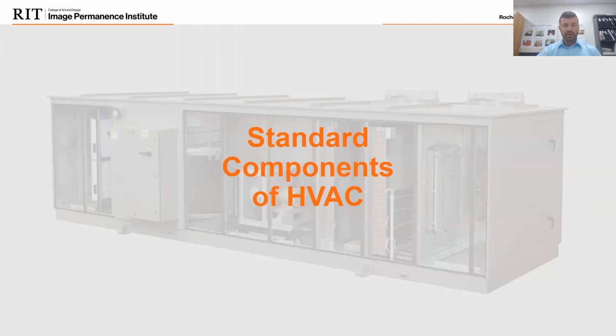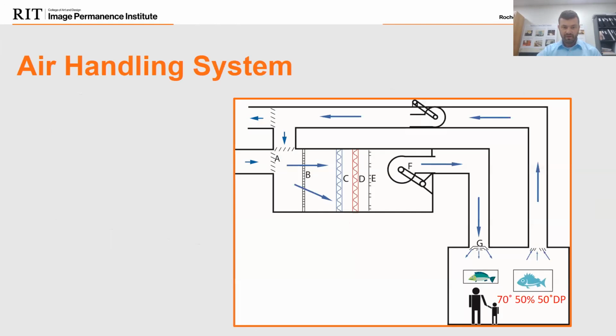So we'll start with our air handling unit. We're going to start with a basic air handling unit. This is what they call a subcool reheat. When we look at this unit, we're going to be dehumidifying the air at the cooling coil, and then heating it back up, possibly humidifying, and sending it back out.